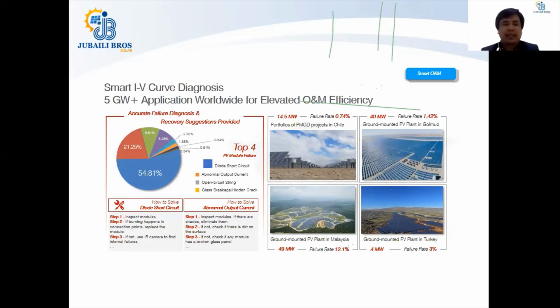And if you do not address such PV plant failures, it will not only decrease the generation of that particular string, but that string can affect the generation of other strings, and over the life cycle, that mismatch of string voltages can reduce more and more generation of your PV plant. So with IV curve tracing, it not only helps you do easy O&M, but it also gives you the benefit of increasing your yield by doing regular checks on your PV strings using IV curve diagnosis, which is a premium feature for the commercial size inverters. But we can provide you a demo on one of your PV project cases on special request.